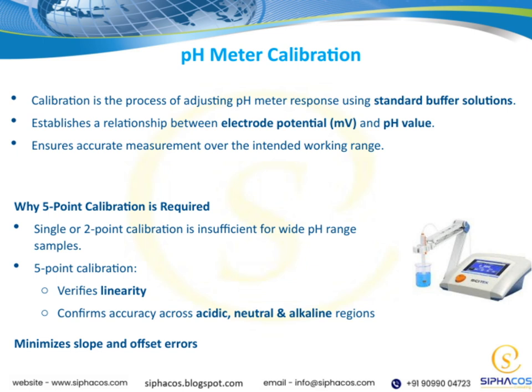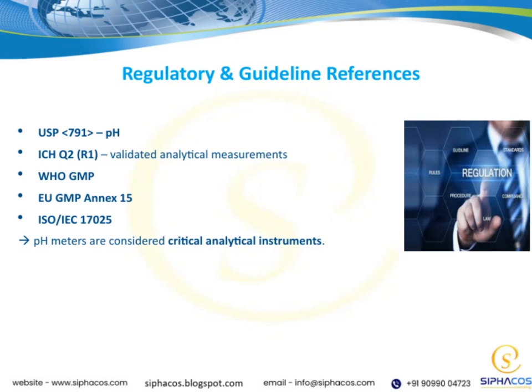Now, calibration in general is about adjusting your pH meter using standard buffer solutions. This process establishes a relationship between the electrode potential, measured in millivolts, and the pH value you're trying to determine. By doing this, you ensure your meter provides accurate measurements within the specific range you're working with, which is essential for reliable analysis. Let's take a moment to look at some of the key regulatory and guideline references that underpin our work with pH measurements.